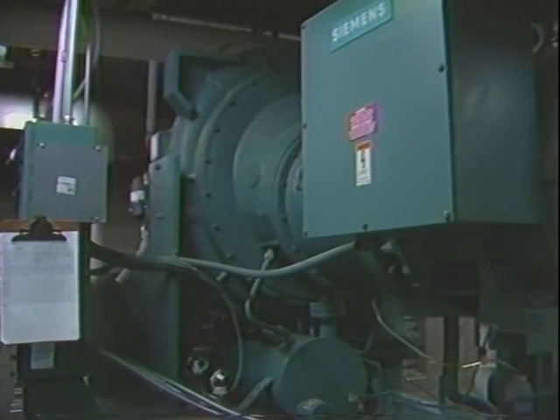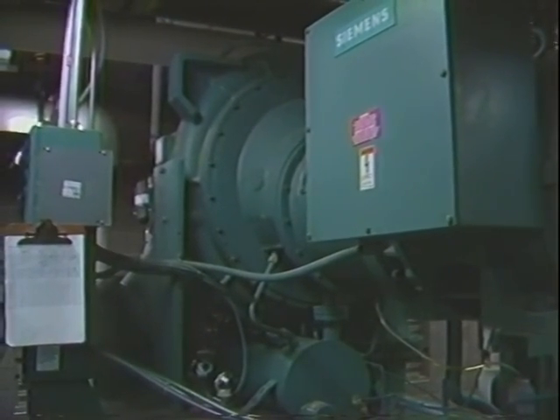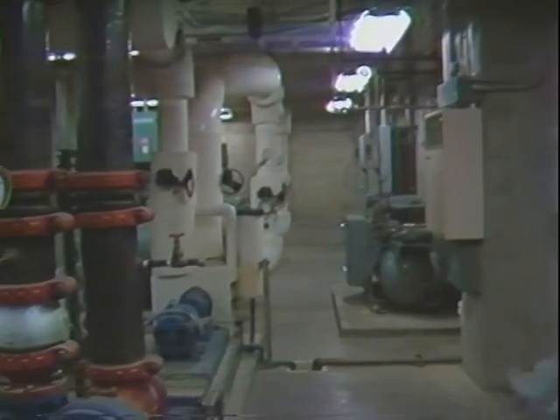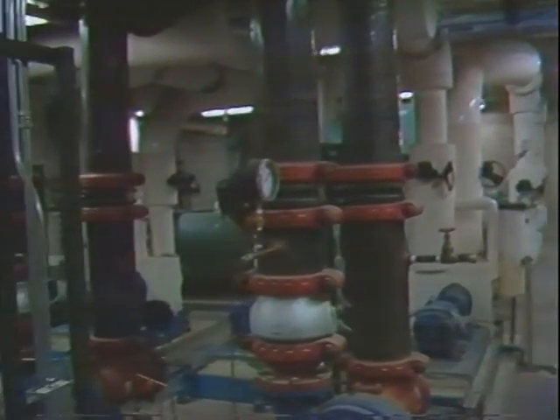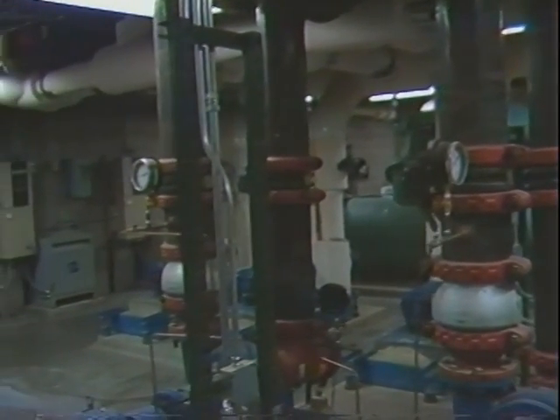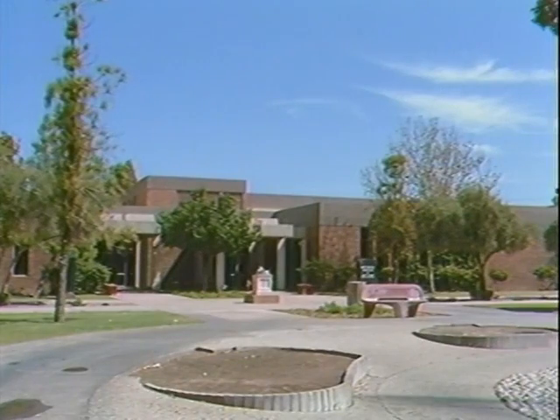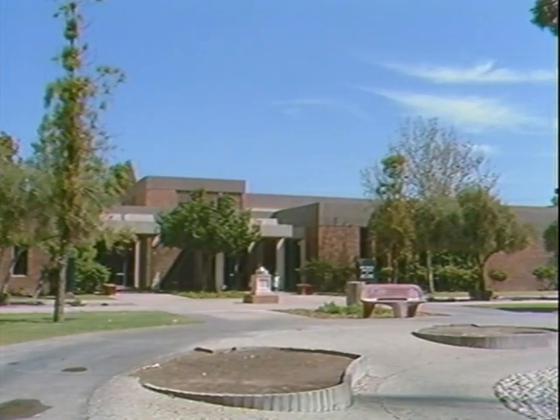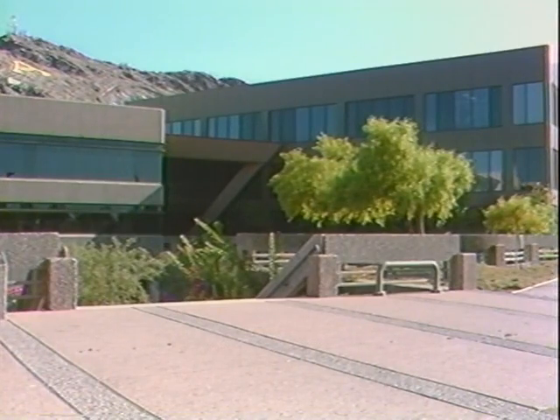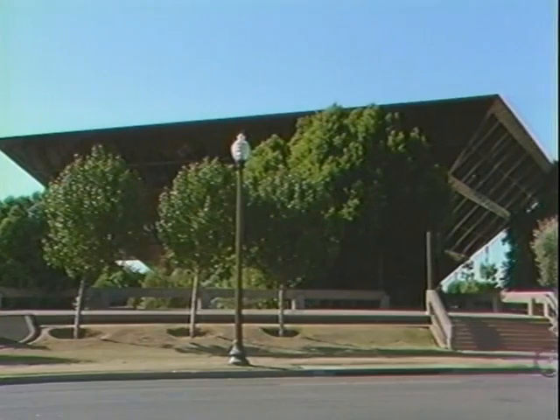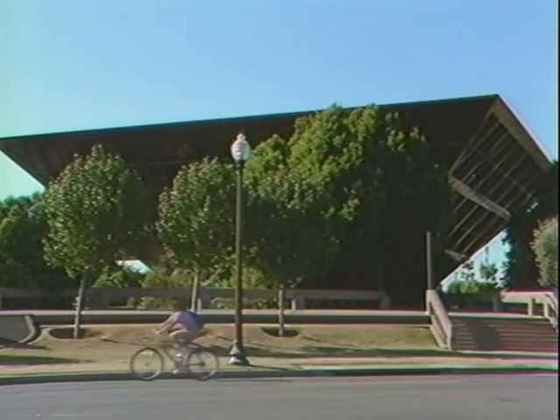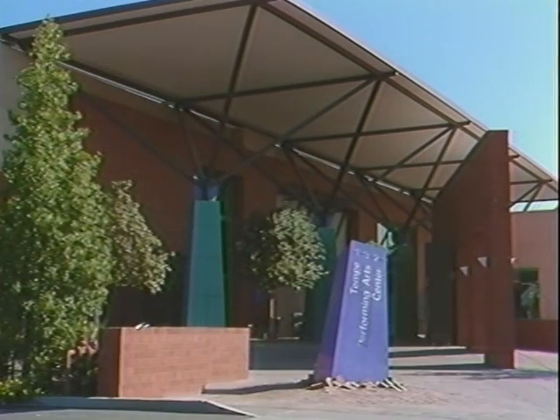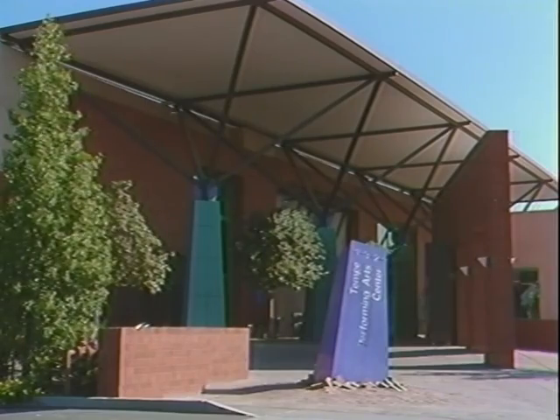The high efficiency of this system allows for district cooling, or using just one chiller to provide water to as many as 3 buildings. For instance, the water chilled in the library is used to cool the air in the Historical Museum as well. And plans are now being made to expand the chilled water system in the police courts building to also cool City Hall and the Performing Arts Center. When completed, 3 separate systems will have been replaced with just one.